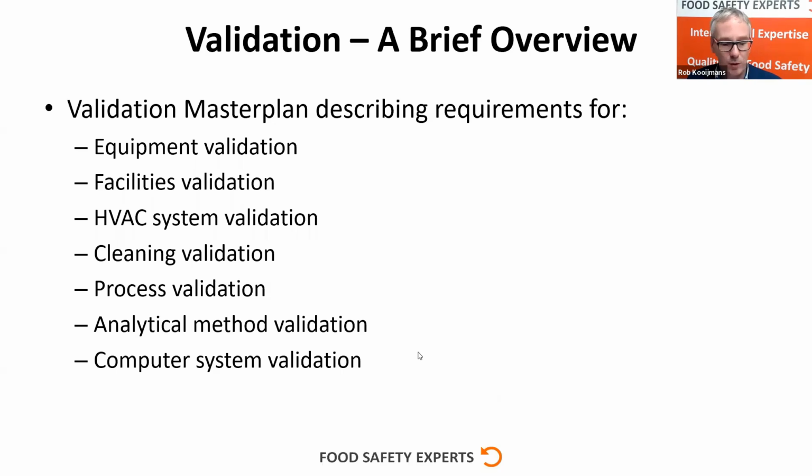If you have specific software written yourself, you actually want to make sure that whatever you put into the software generates the right outcome in all circumstances. So that's something that also certainly for pharmaceutical companies and medical equipment companies needs to be part of the overall validation master plan, and needs to be validated.